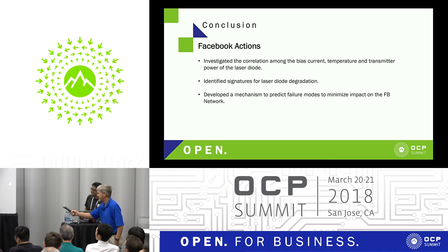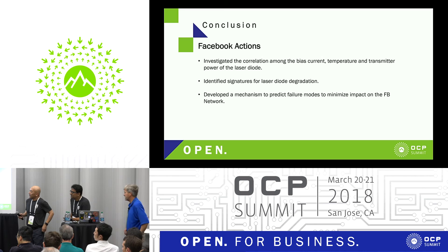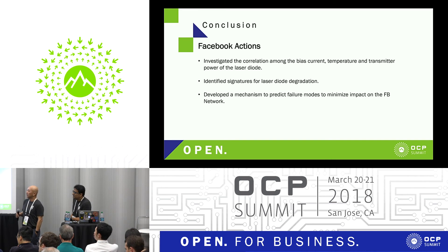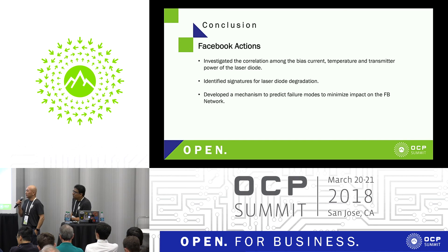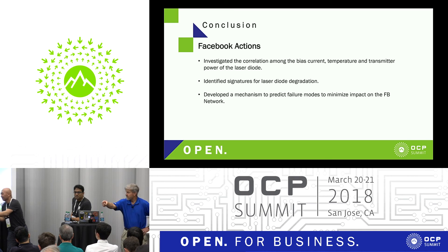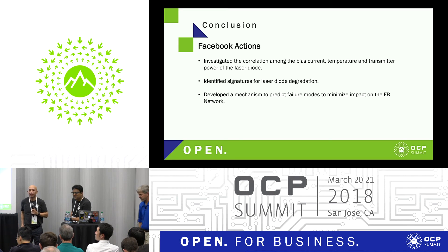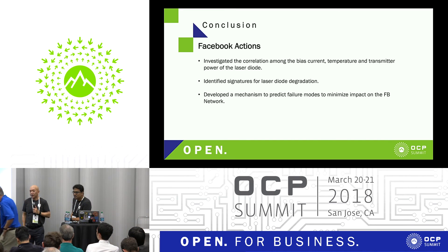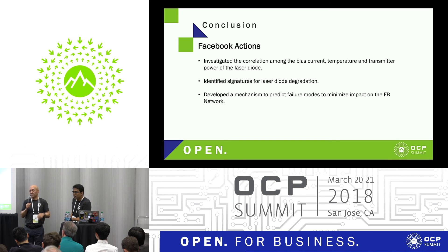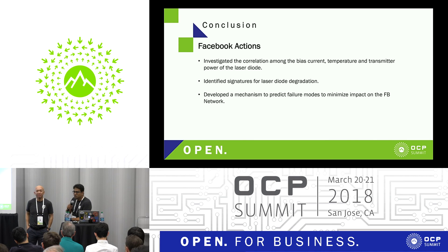During Q&A, one question asked whether failures were observed where power did not decrease but the relaxation oscillation frequency decreased — the answer was no, we don't see these things. Another question asked whether it is possible to monitor the spectrum. The answer was that spectrum monitoring would be very challenging because the method here uses EEPROM recording via I2C, and the spectrum is not recorded. Basically, whatever is available inside the DOM can be read to get those parameters and predict failures with this kind of tool.